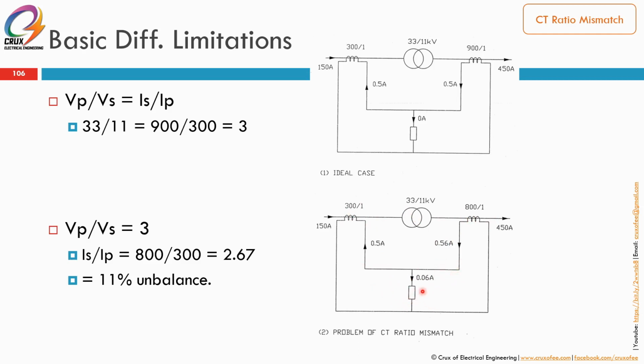It may not reach the setting, or it may. Under normal current there may be no issue, but say a high fault current outside the zone: this can be 0.6 or 1 to 2 amps. So it can trigger false tripping due to an external fault because of this CT mismatch issue. CT ratio mismatch, so that is problem number 1.